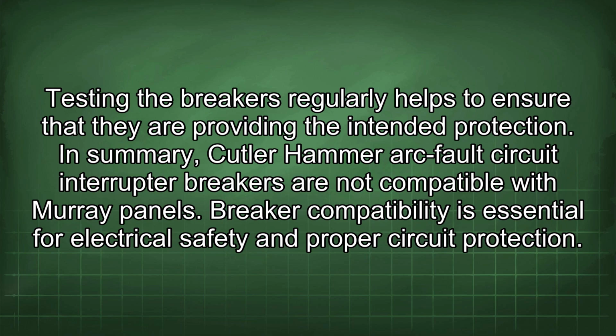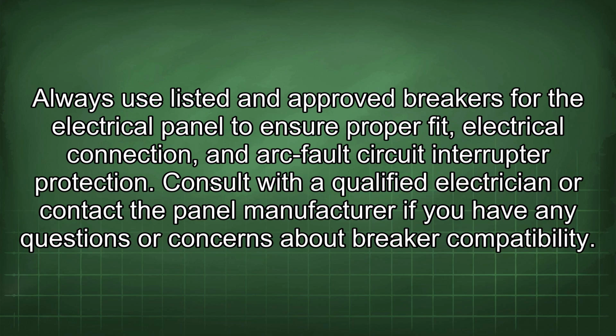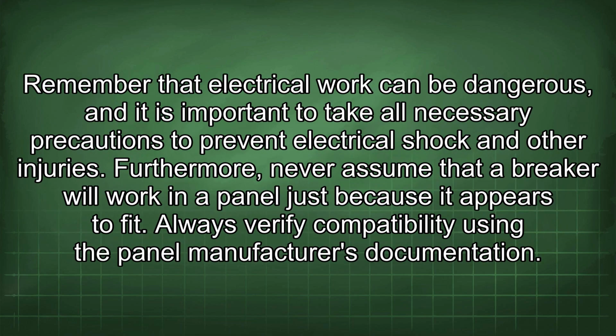In summary, Cutler Hammer arc fault circuit interrupter breakers are not compatible with Murray panels. Breaker compatibility is essential for electrical safety and proper circuit protection. Always use listed and approved breakers for the electrical panel to ensure proper fit, electrical connection, and arc fault circuit interrupter protection. Consult with a qualified electrician or contact the panel manufacturer if you have any questions or concerns about breaker compatibility. Remember that electrical work can be dangerous, and it is important to take all necessary precautions to prevent electrical shock and other injuries.